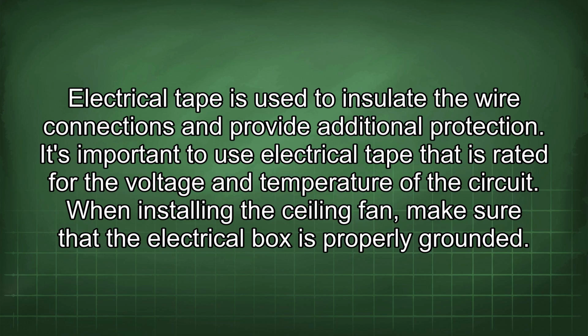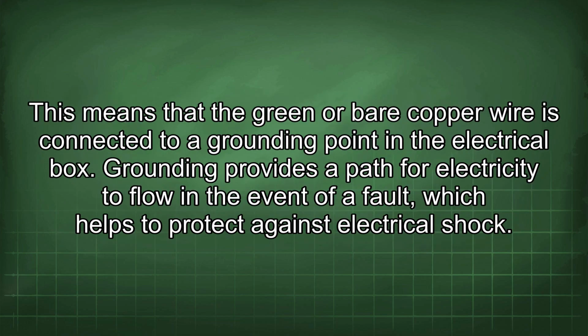When installing the ceiling fan, make sure that the electrical box is properly grounded. This means that the green or bare copper wire is connected to a grounding point in the electrical box. Grounding provides a path for electricity to flow in the event of a fault, which helps to protect against electrical shock.